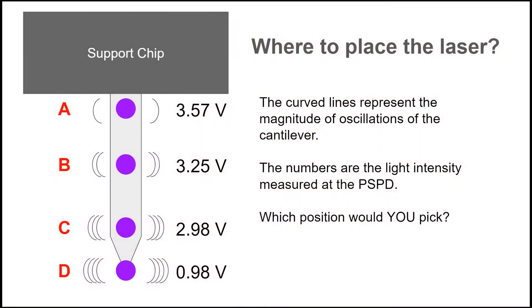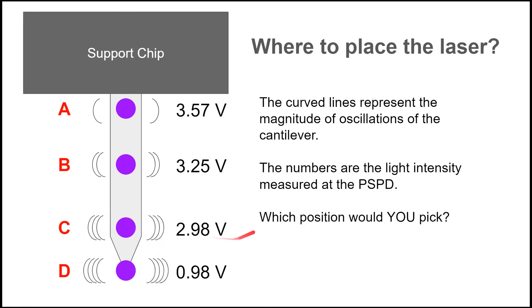In the previous video, it was difficult to see the laser as it moved down the cantilever. A cartoon shows a laser spot at four potential points along the cantilever. The intensity of the laser light decreases as you move down the cantilever, whereas the magnitude of the oscillations increases as you move down it. The optimal laser point is around point C, where the intensity is still quite high and the oscillation amplitude is also sufficient for good measurements.